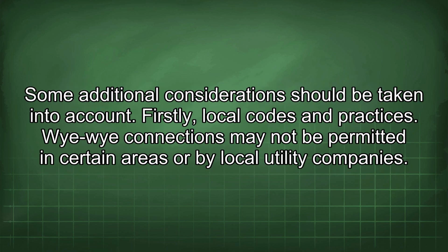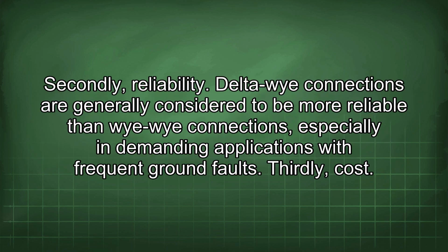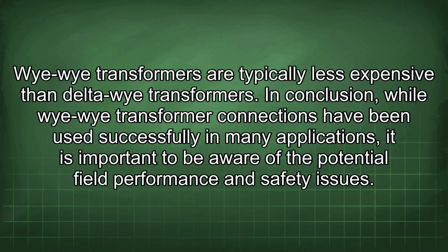Some additional considerations should be taken into account. Firstly, local codes and practices. Wye-Wye connections may not be permitted in certain areas or by local utility companies. Secondly, reliability. Delta-wye connections are generally considered to be more reliable than Wye-Wye connections, especially in demanding applications with frequent ground faults. Thirdly, cost. Wye-Wye transformers are typically less expensive than delta-wye transformers.